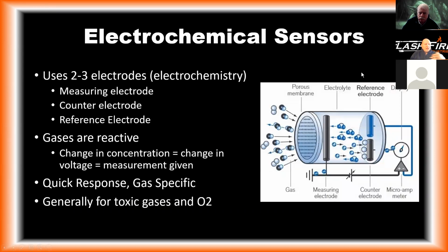So then the specific sensors that we're talking about. We have basically 4 main sensors. We're going to touch on 4, but 3 is what you guys use. So we have electrochemical sensors. This uses 2 to 3 electrodes. Toxic gases are reactive, and so as more gas enters the electrode, it changes the voltage, and that's what gives us a measurement, okay?